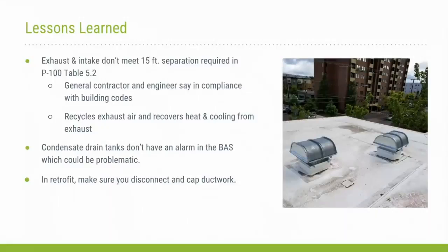So we talked about the condensate drains. One of the issues we had in the building was because we were able to disconnect the old system, they didn't properly disconnect it completely. They just used the OBDs, and air bled by, and you could hear it. So you got to actually cap the ductwork. Next slide, please.